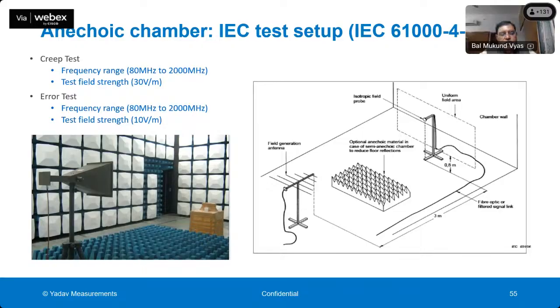The field strength is 10 volts per meter, and the accuracy of the meter is tested in the presence of this kind of field. Generating this kind of field requires different kinds of antenna. This is a very expensive test and also time consuming. The antenna has to be kept at 3 meter distance from the meter itself.